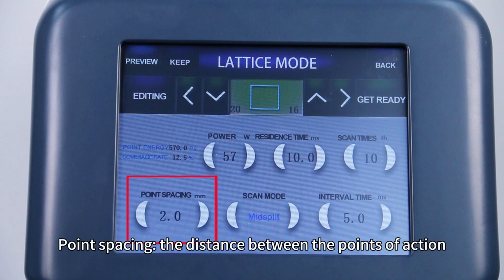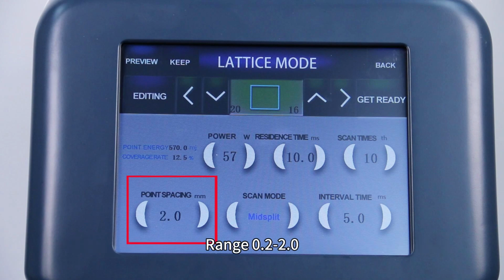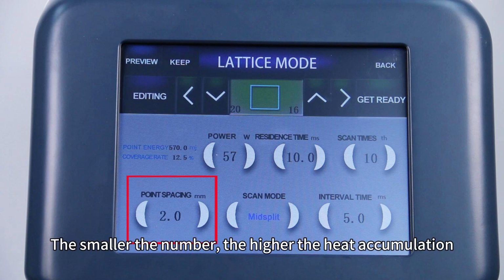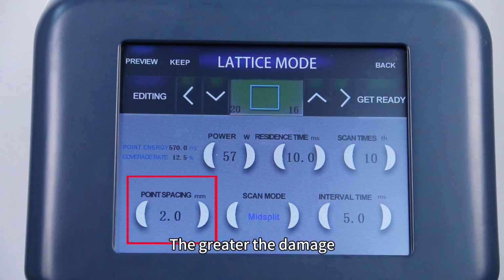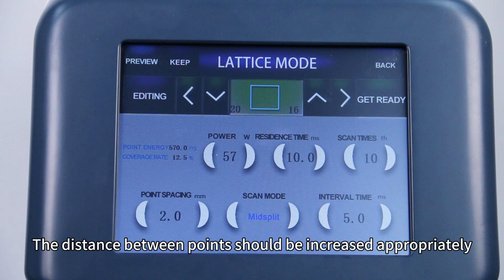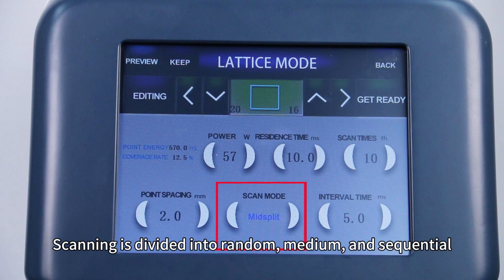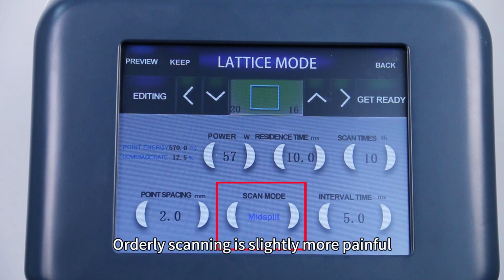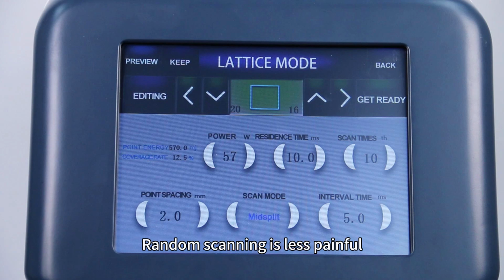Point spacing is the distance between the points of action. Range 0.2 to 2.0. 0.2 is most dense, 2.0 most sparse. The smaller the number, the higher the heat accumulation, the greater the damage, but the better the effect. When the energy is higher, the distance between points should be increased appropriately. Scanning is divided into random, medium, and sequential. Orderly scanning is slightly more painful. Random scanning is less painful.